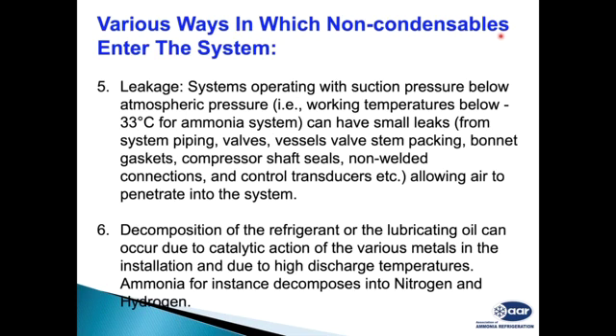Another thing which may happen is leakages. When our plant is operating and suction pressure is below atmospheric pressure, it is typically below -33 degrees centigrade. And if there is a small leak, whether in the piping or the valves, flanges, valve gaskets, or the glands, stems of the valve, compressor shaft seal, or sensors like temperature sensors connected through sockets. If the plant is in vacuum, it means the pressure inside the plant is lower than the atmospheric pressure. Then atmospheric air will enter into the plant.